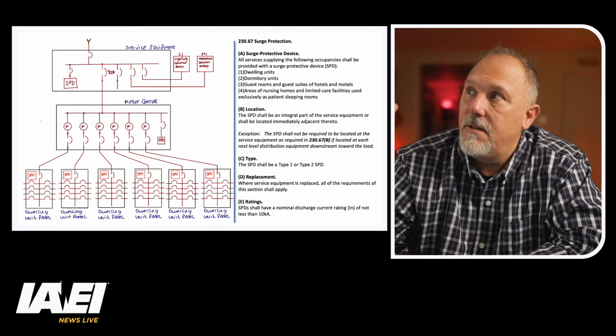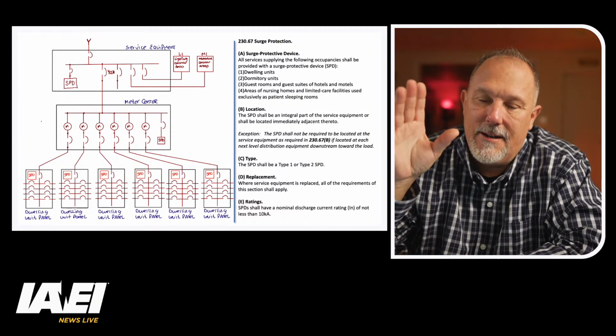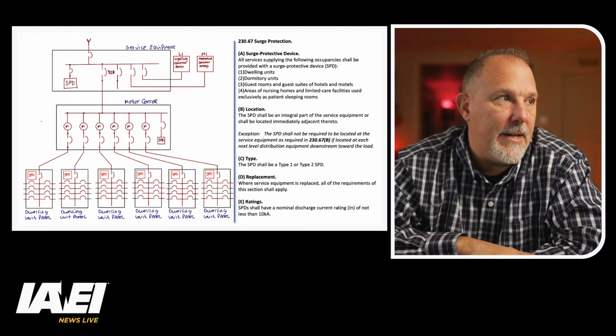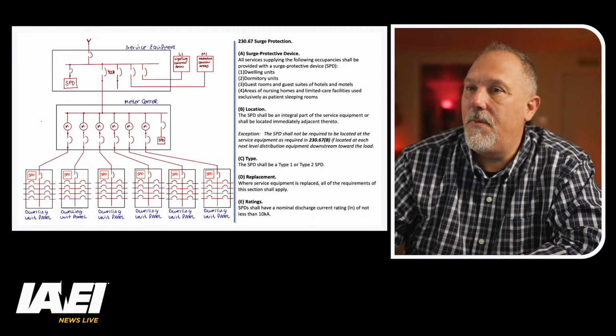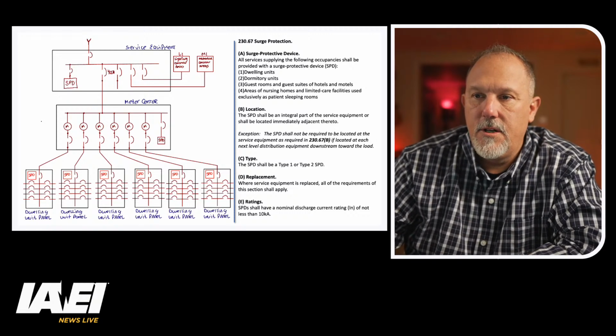So that's basically how that reads. I hope that sort of makes sense. But I think that's missed a lot. I think a lot of inspectors would just go down to the dwelling unit and say, okay, you've got surge at the dwelling unit, and then I'm not going to worry about the meter center or the service equipment, or those lighting panels, or that mechanical panel. And honestly, I can't say whether or not that's okay. I can just tell you that that would be a code violation.